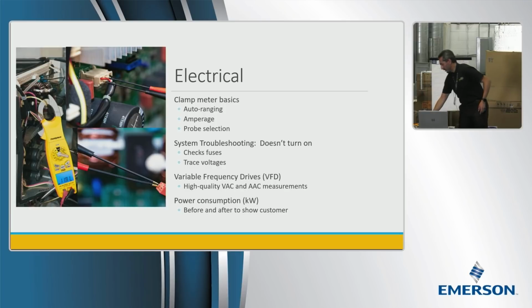So you want to find a meter that has a low-pass filter built in for voltages and amperages, so when you take those measurements it'll filter out the noise of that signal and help you get a more accurate measurement on variable frequency drives.